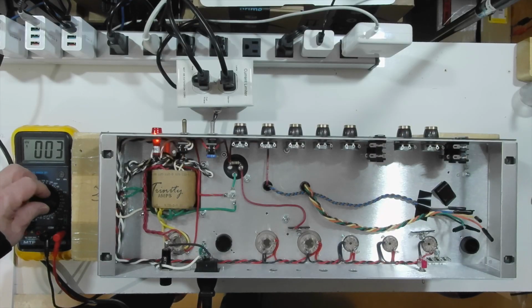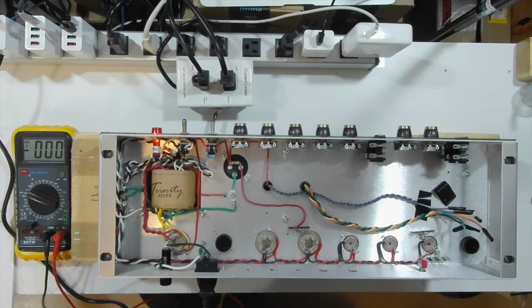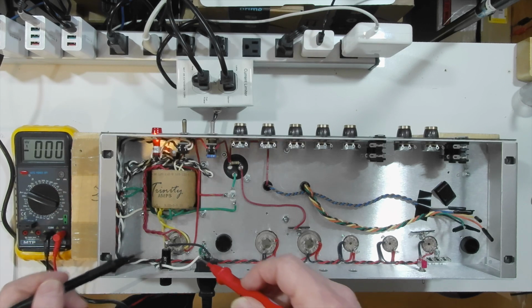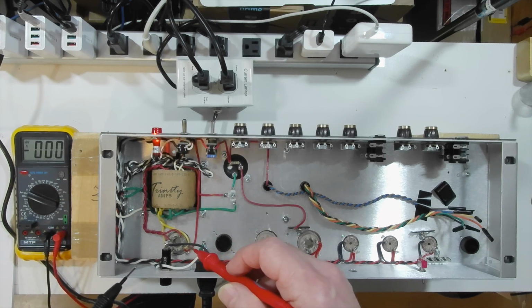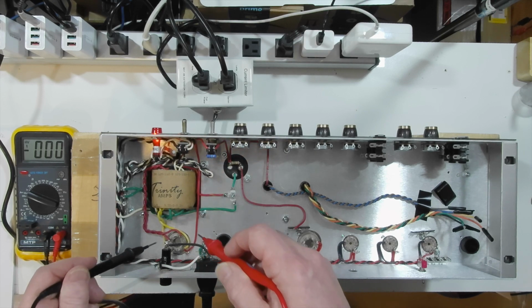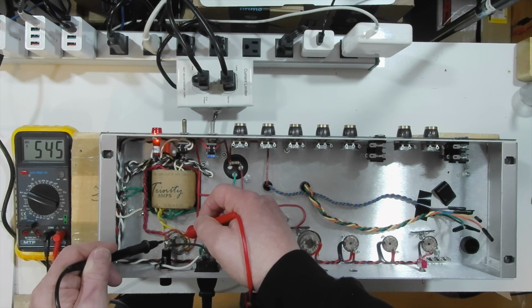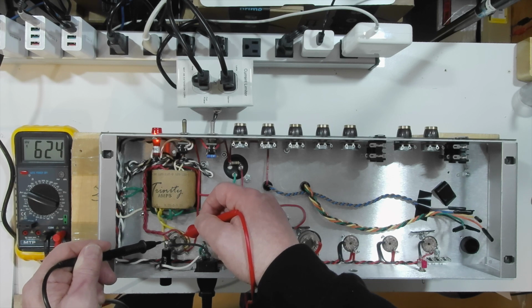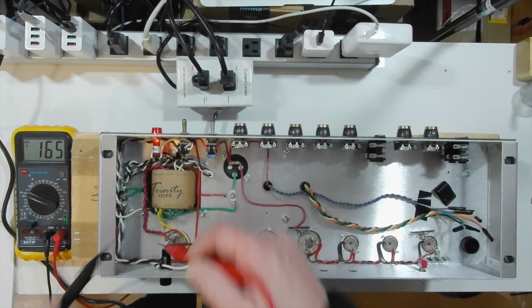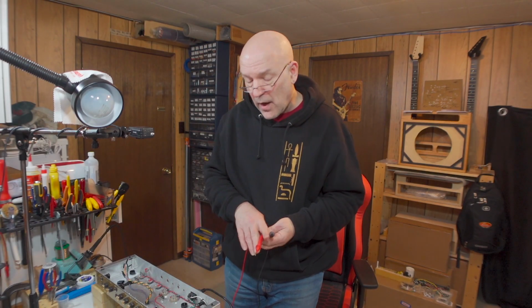Switch your meter to the 700 volt range, and we're going to measure the voltage across pins 4 and 6 of the rectifier socket. There we go, we're getting 625 volts AC. That's what we expect, so the high voltage winding is good too.